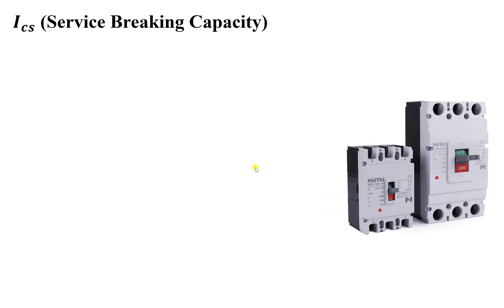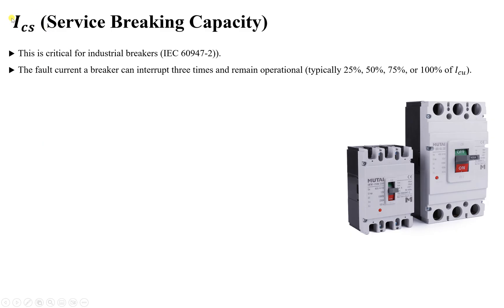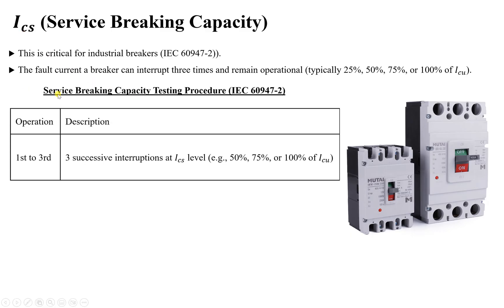The next value is ICS — the Service Breaking Capacity — which we have just seen on the nameplate. This is critical for industrial breakers per IEC 60947-2. The ICS value on the circuit breaker means the breaker can interrupt that fault current at least three times and remain operational. Typically ICS is given as 25%, 50%, 75%, or even 100% of ICU, and the breaker must withstand this value at least three times.